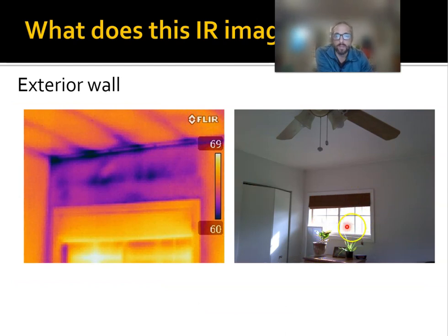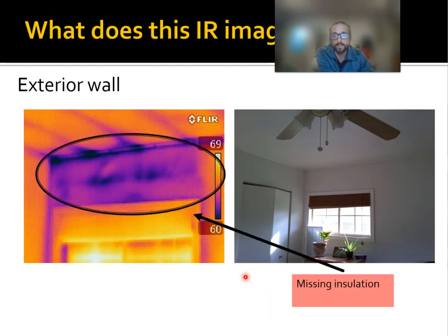This is the same house. This is obviously an exterior wall. We have a window, and you look at the image here. So see if you can think about what's happening. Again, we know building framing, so we know what's going on up here. We should have a header right here. There's probably little tiny stud bays between these cripple studs, right? And they probably just didn't insulate it. So this home was built in the 50s, and insulation was not as big of a concern.